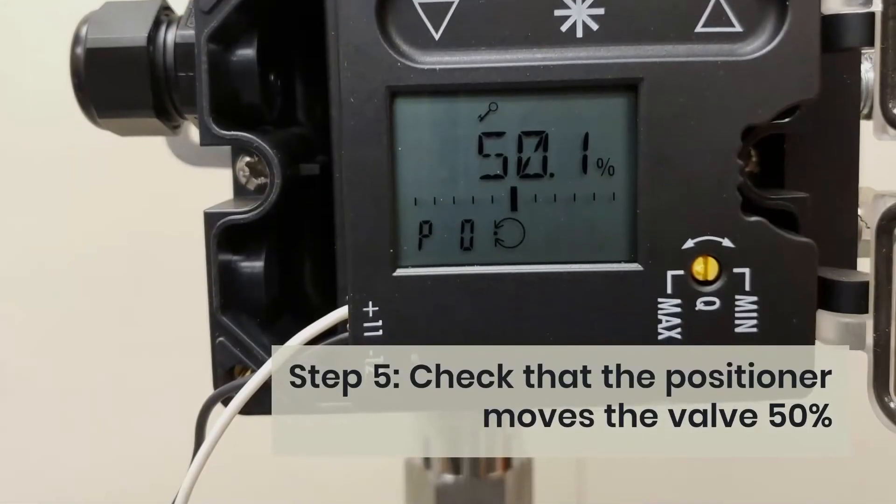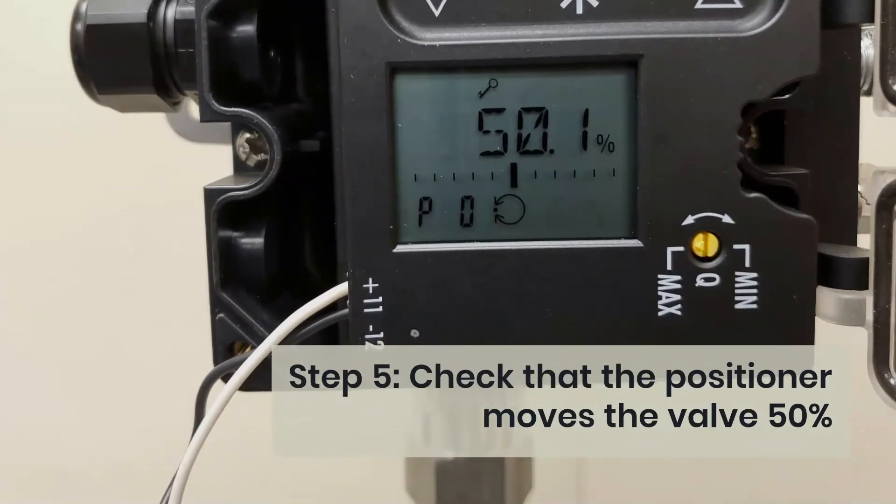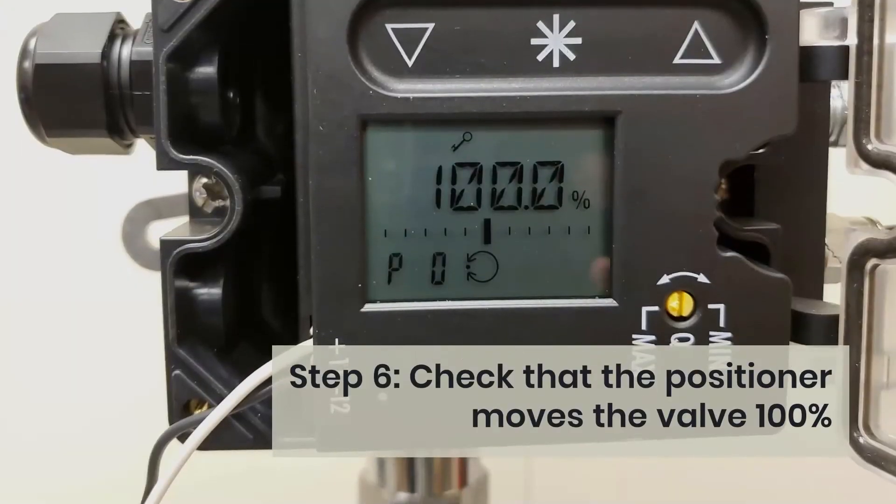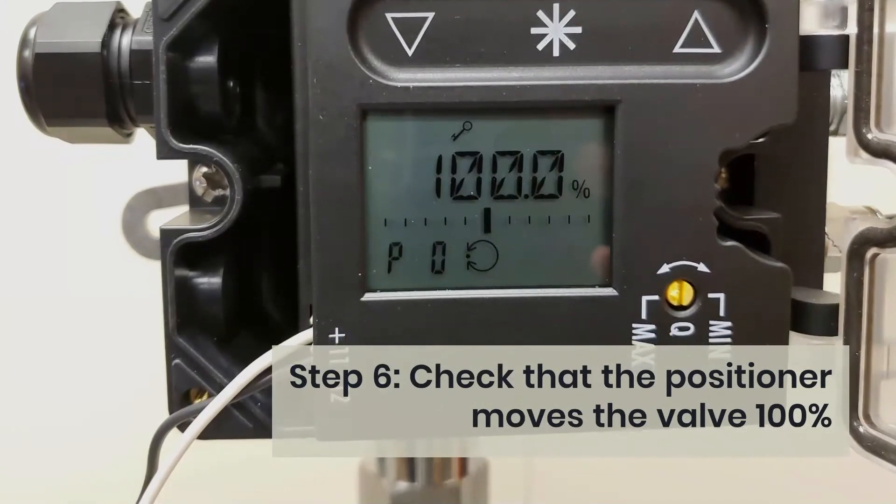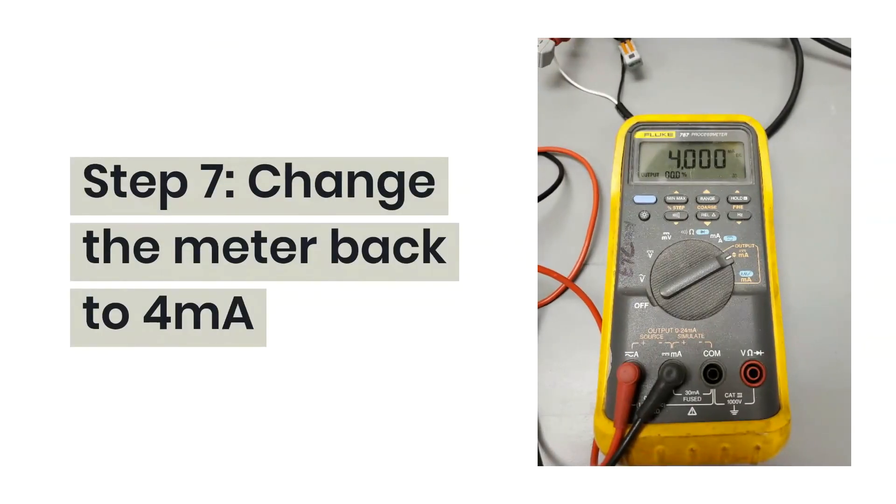Step 5: Check that the positioner moves the valve 50% by changing the meter from 4mA to 12mA. Step 6: Check that the positioner moves the valve 100% by changing the meter from 12mA to 20mA. Step 7: Change the meter back to 4mA.